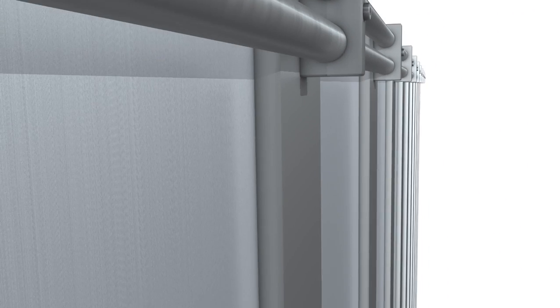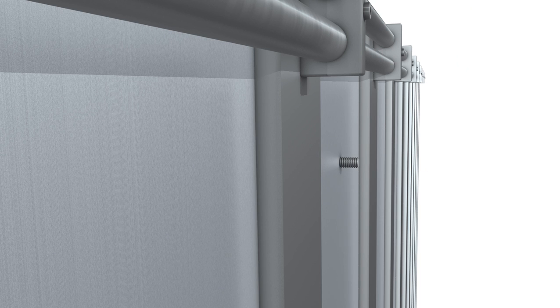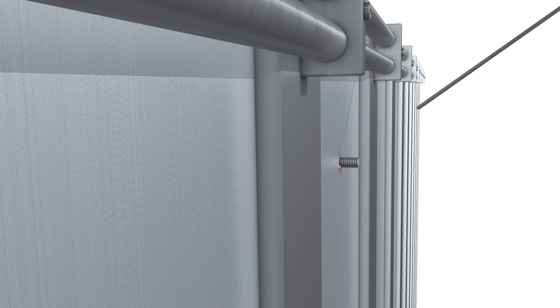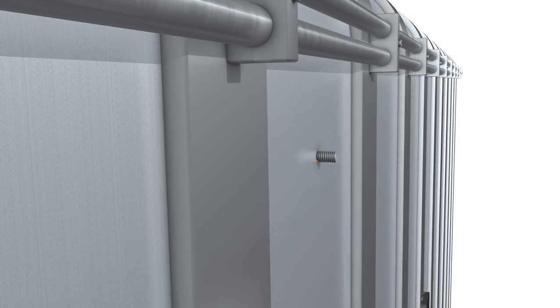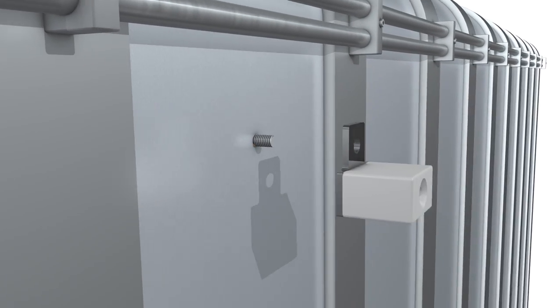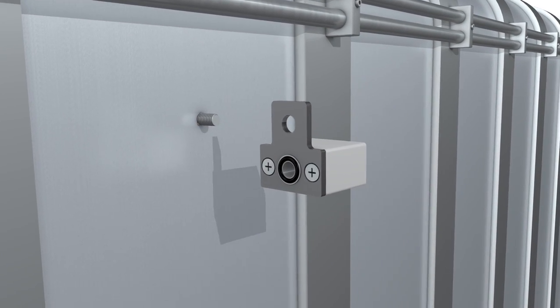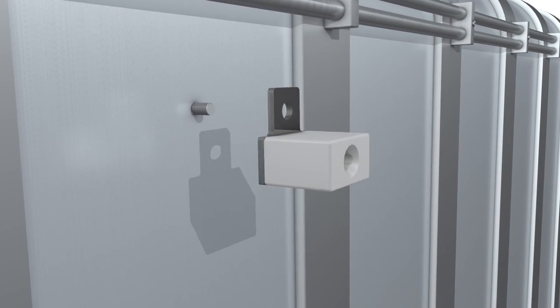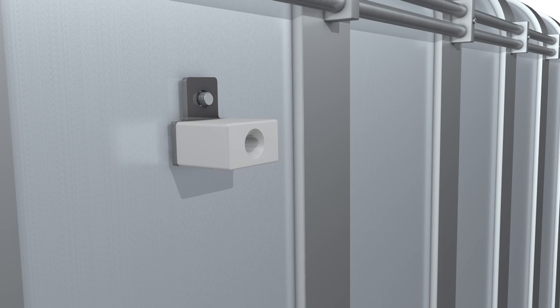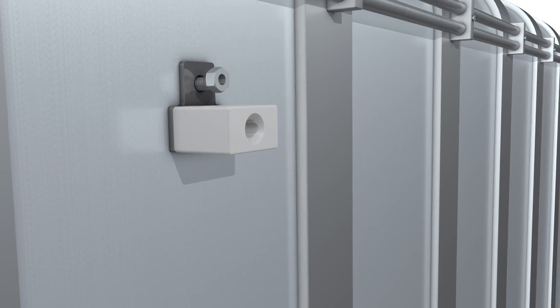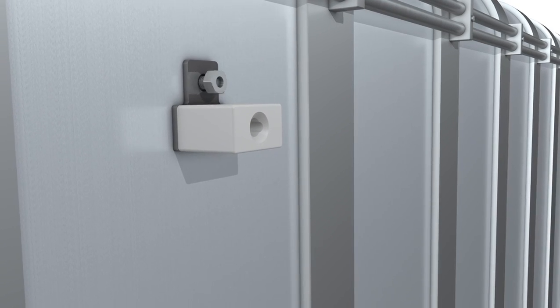A tank solution is available whereby the device is bolted to a weld stud on top of the tank wall. This easy to handle solution is shown here. The stud is welded to the tank, the clamp block is tightened down, and the measuring device can be inserted.